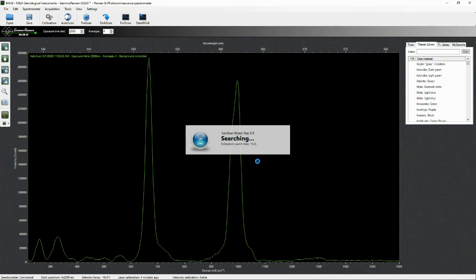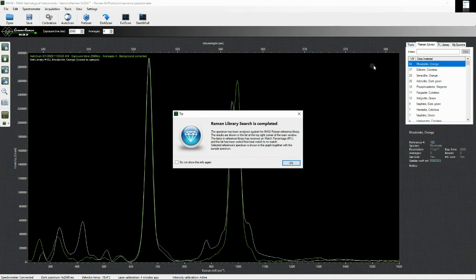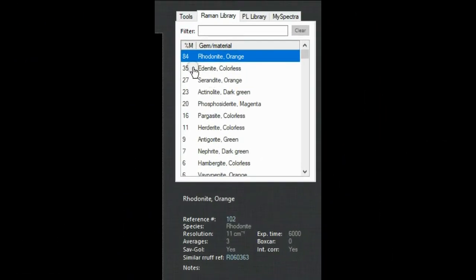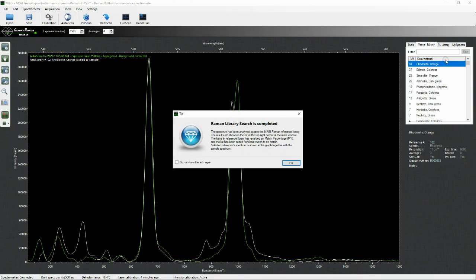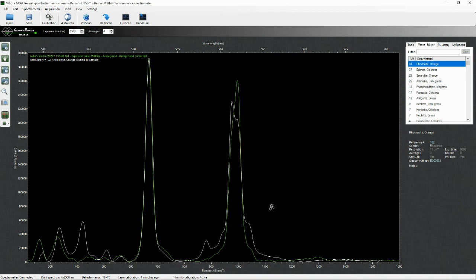The library listing is sorted so the best matches are shown first. The spectrum of the best matched library item is also automatically opened as a white reference spectrum for visual inspection. The operator can check each reference against the green sample spectrum by clicking the reference name on the list or moving on the list with the keyboard arrow keys.